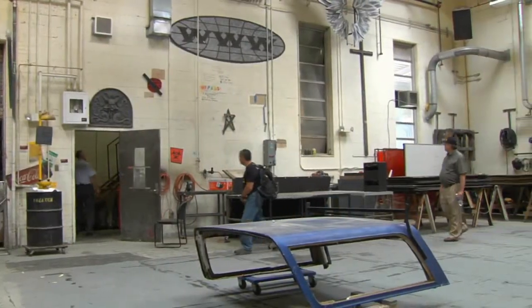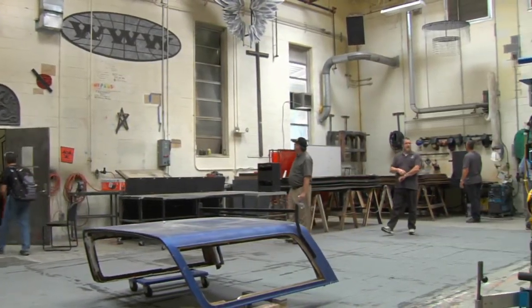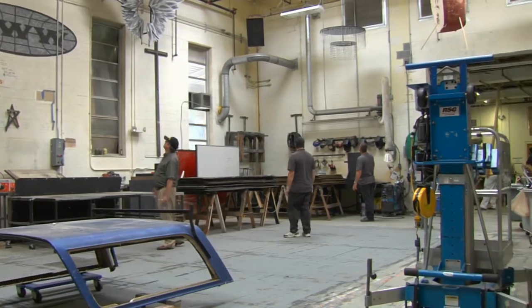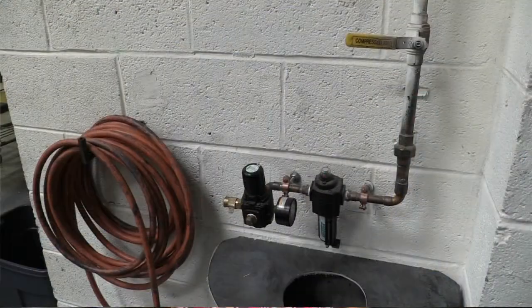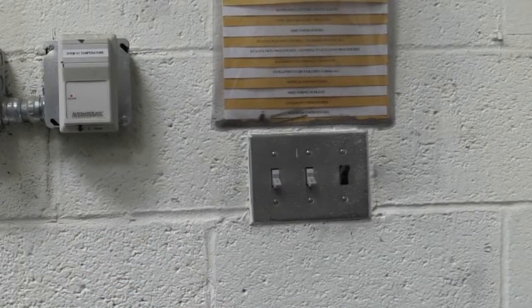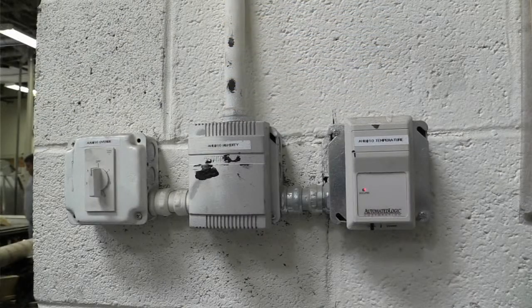So we're in the metal shop, and next door was a wood shop. They both have compressed air. They both have lighting controls that appear to be occupancy sensor based or manual light switches. They have dedicated HVAC systems. So what we're really saying is that there's an opportunity to optimize your BAS and either set it up so the schedules are significantly tighter, or put an occupancy sensor in here that would override the schedule.